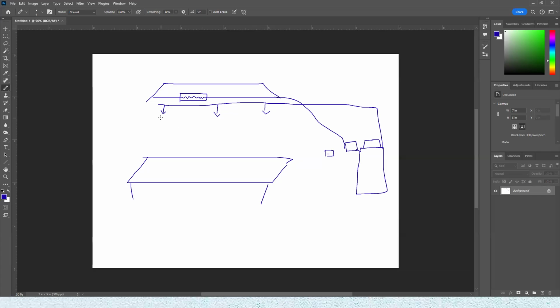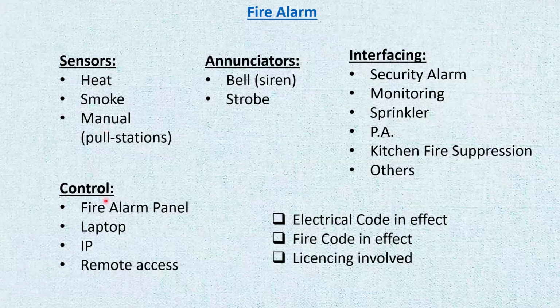And when that finishes, because the hot plate can still be hot, the fire can reignite. So after that, water comes down to cool the plate down, right? So the fire doesn't reignite, and it's all sequenced and timed. So that would also be kitchen systems. I don't think I have, yeah, kitchen fire suppression here.